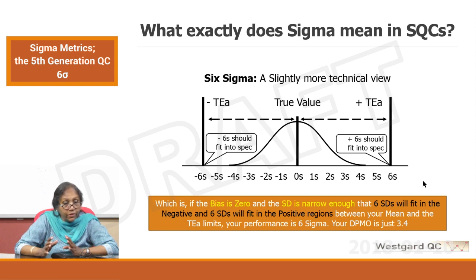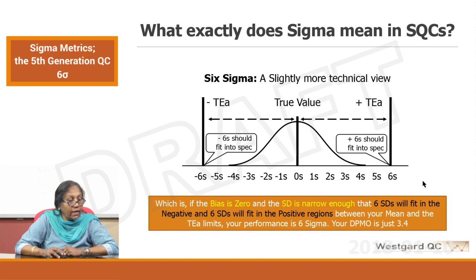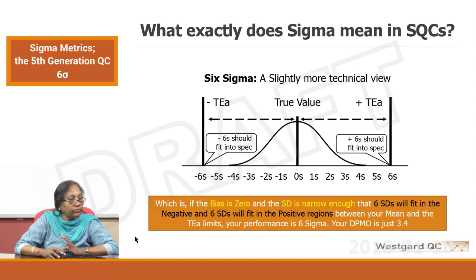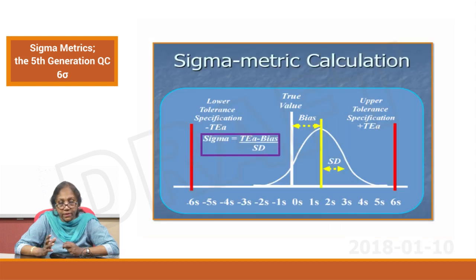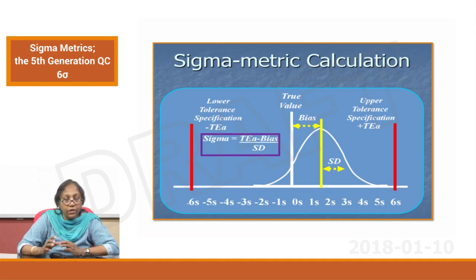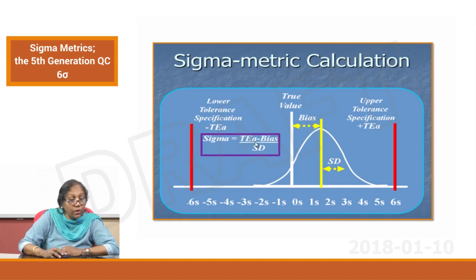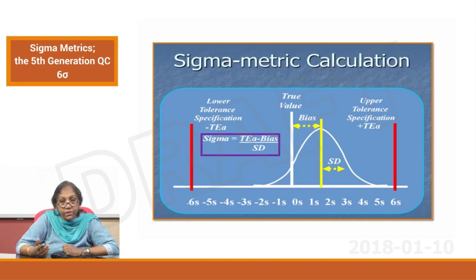To get a 6 sigma you need to have your bias really controlled and your imprecision really controlled, so your DPMO is only 3.4 per million operations. There should be some way of calculating it. Sigma equals total allowable error minus bias, divided by standard deviation. If you are calculating it in units you can do it; also in percentages — we will talk about it now.